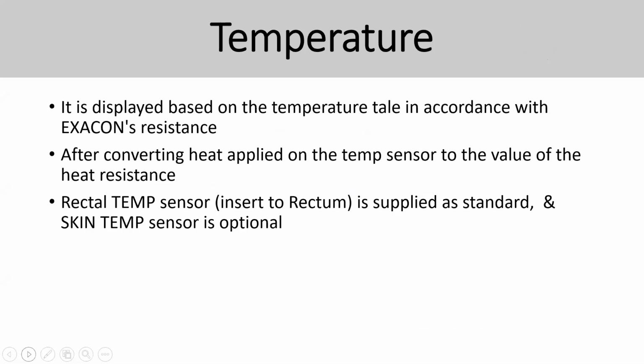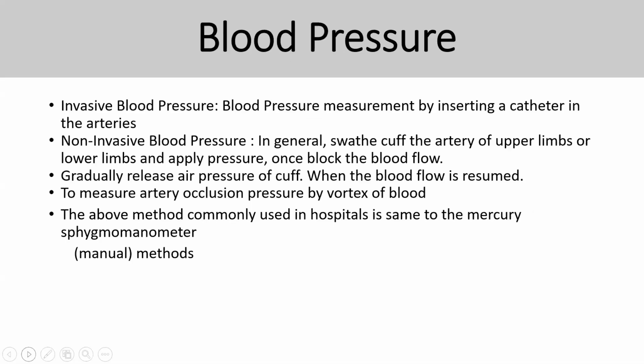Temperature is one of the key factors because you need to measure the temperature of the patient. So on most of the devices you're normally going to see temperature 1 and temperature 2. It is basically attached to the skin, and you can monitor the temperature of the body, all that. Blood pressure. So you've got two types of blood pressure monitoring. One is invasive type, another one is non-invasive. Non-invasive basically uses a cuff, and invasive is basically inserting a catheter line in the artery. So it's going to measure by using a pressure sensor.